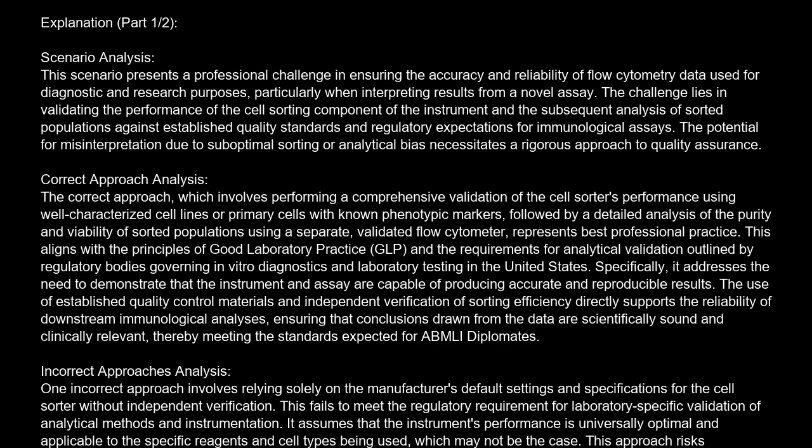Correct answer is B. Conduct a comprehensive validation of the cell sorter's performance using well-characterized cell lines or primary cells with known phenotypic markers, followed by quantitative assessment of the purity and viability of sorted populations using a separate, validated flow cytometer. Explanation. Scenario analysis.